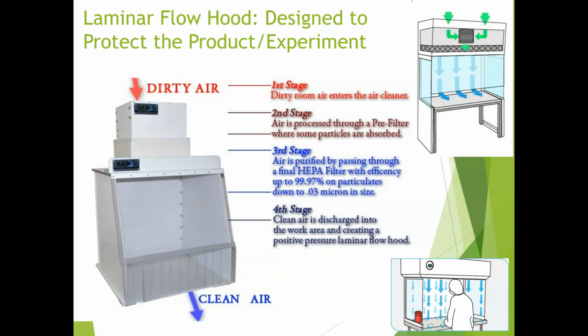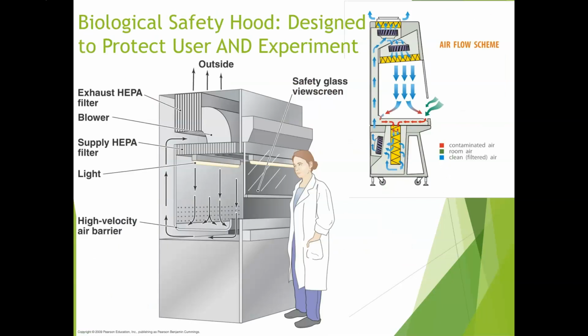The laminar flow is different from a typical biological safety hood. Biosafety hoods protect the experiment and the experimenter. This requires a more complex design to control the flow of air. Air is drawn in from the edges of the hood, including one near the experimenter. This is sent through a high-efficiency particulate air, HEPA, filter before being directed down into the hood space. Air is vented out of the hood as well after it goes through another HEPA filter. Study these diagrams in order to understand this setup.